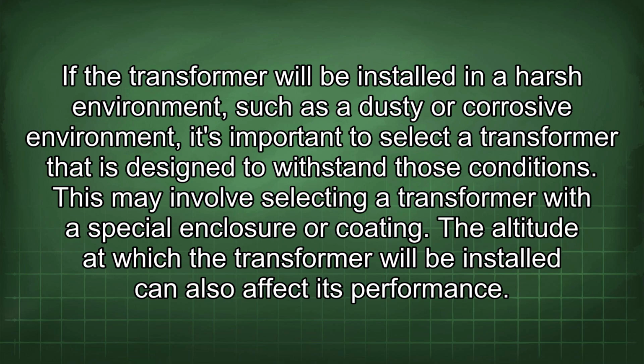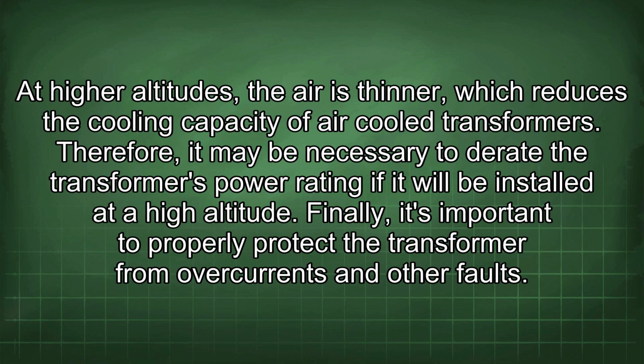The altitude at which the transformer will be installed can also affect its performance. At higher altitudes, the air is thinner, which reduces the cooling capacity of air-cooled transformers. Therefore, it may be necessary to derate the transformer's power rating if it will be installed at a high altitude.